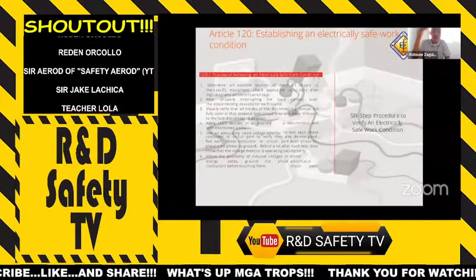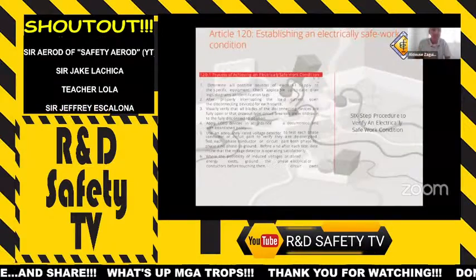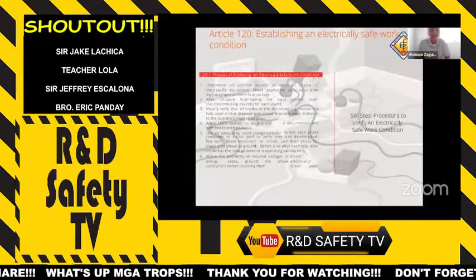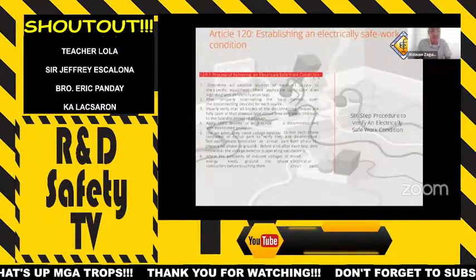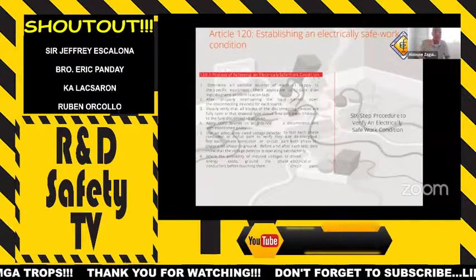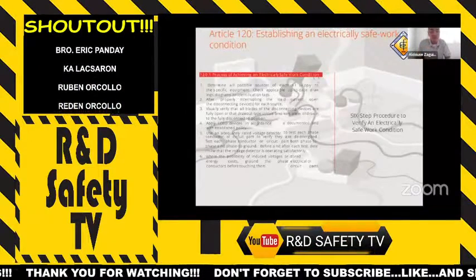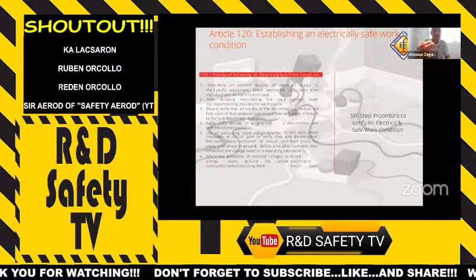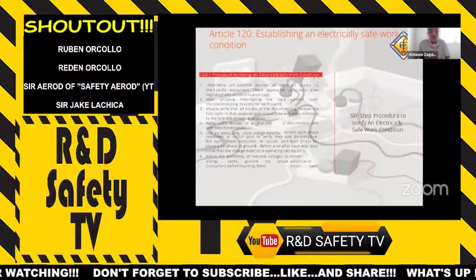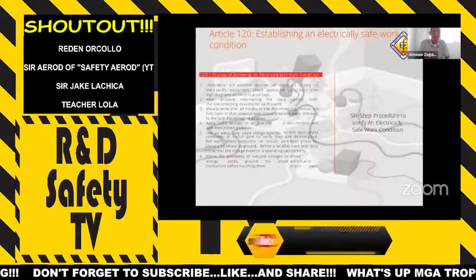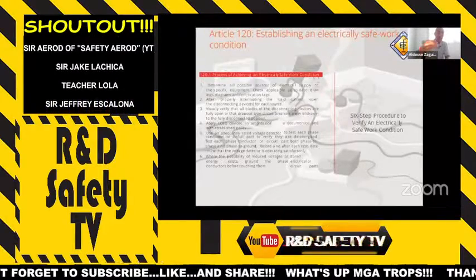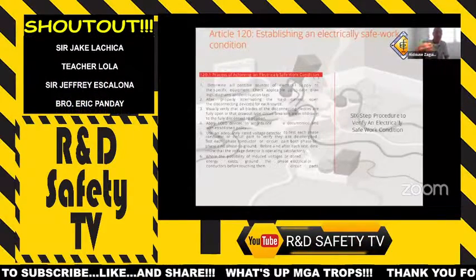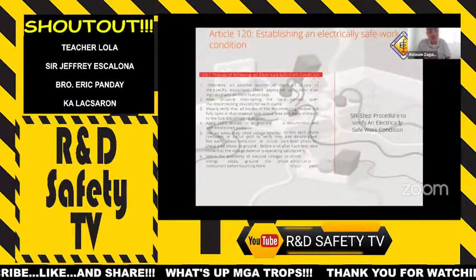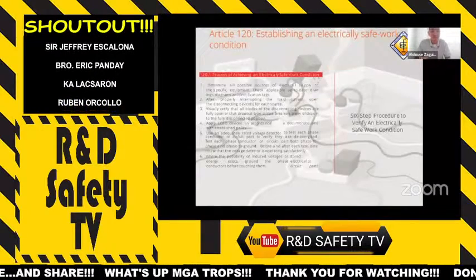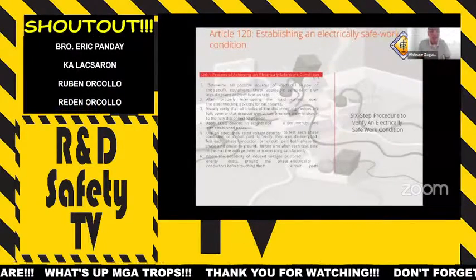So you have to identify all possible sources—it's not always just one. Then you interrupt the load by disconnecting devices. Commonly this is the breaker, which serves as your disconnecting means and overcurrent protection for the circuit. But it's not always like that—sometimes there are just fuses that aren't used.